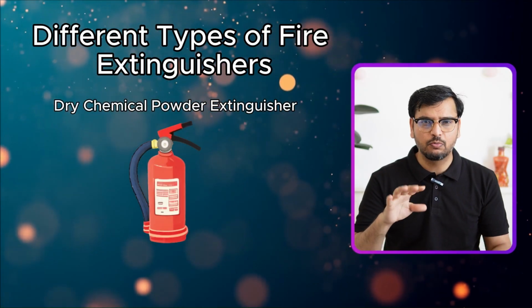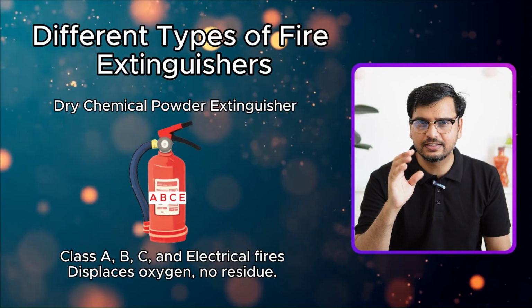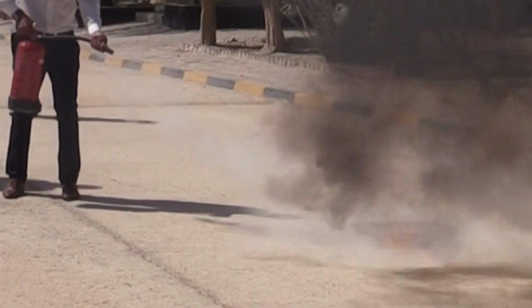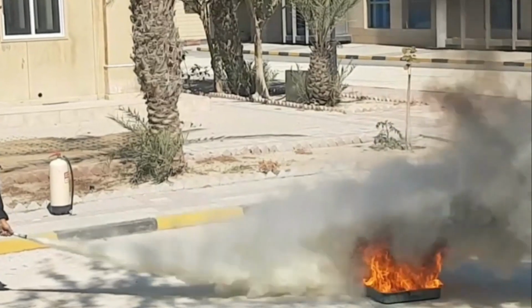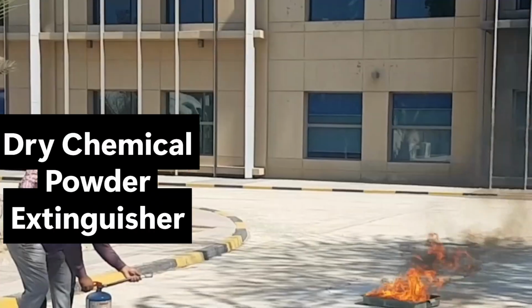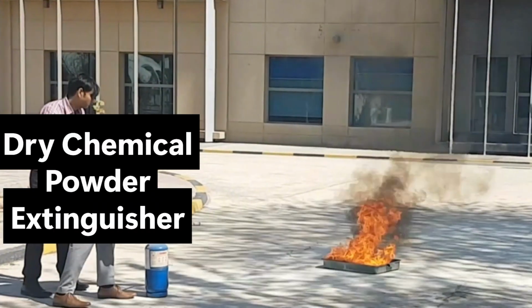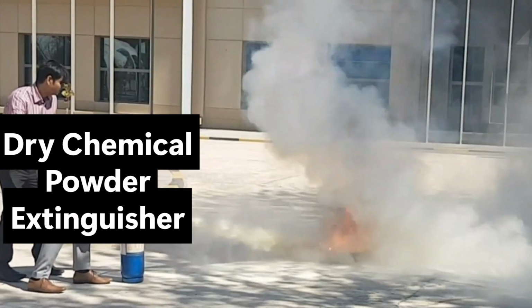Now let's look at dry chemical powder extinguisher. Dry powder extinguishers are versatile and can be used on class A, B and C as well as electrical fire. They work by smothering the fire and stopping the chemical reaction. However, they can be messy and may not cool the fire completely.